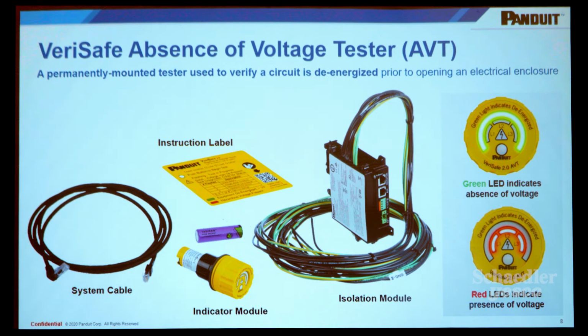You can get different accessories too for it, but basically you have a 30 millimeter knockout indicator module at the door. You have a communication cable going back to the isolation module. The isolation module is DIN rail mounted or flush mounted on the back panel. You'll see all the leads coming out of that isolation module. They're 2 leads per phase and 2 leads to ground. So you have 8 wires to connect into the system.